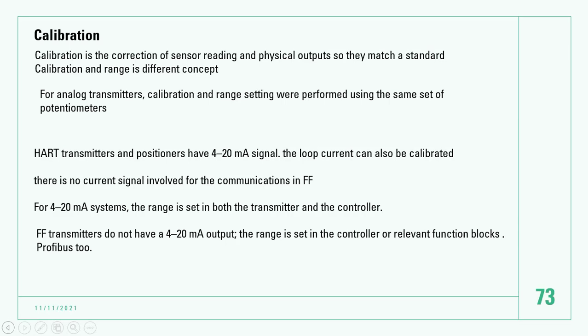Calibration and range setting were performed using the same set of potentiometers. HART communication uses the 4 to 20 mA signal. The loop current can be calibrated. See, HART just calibrates the loop current. Okay, but in Foundation Fieldbus there is no current signal.